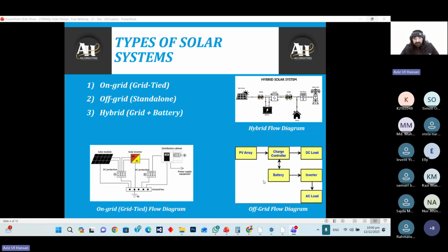And the other part is the off-grid or standalone systems. Basically, the standalone system has only the PV, charge controller and battery available. No grid is available. The PV array is sent to the charge controller or the off-grid inverter, and that off-grid inverter will charge the batteries, and supply the DC loads or the AC loads through the inverter. But now, mostly in the off-grid or standalone inverters, the charge controller is built in within the inverter.